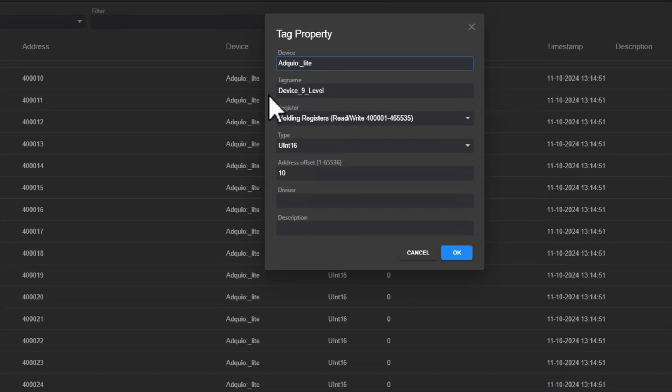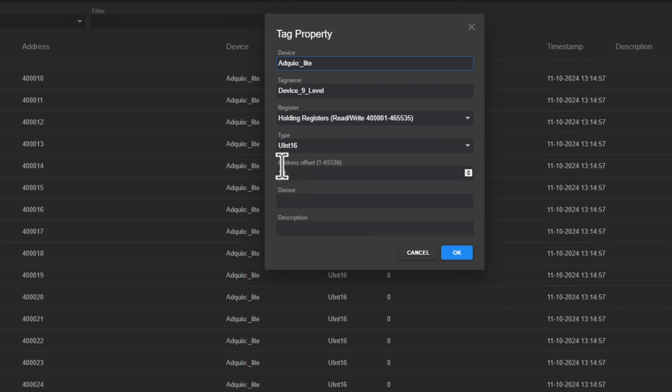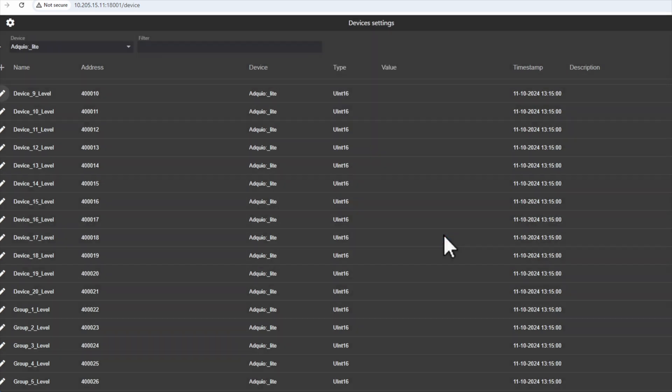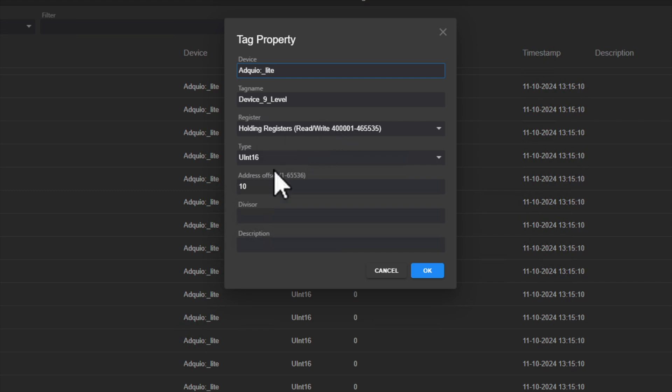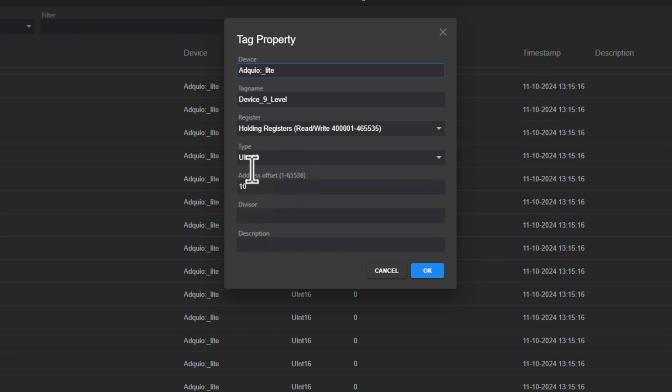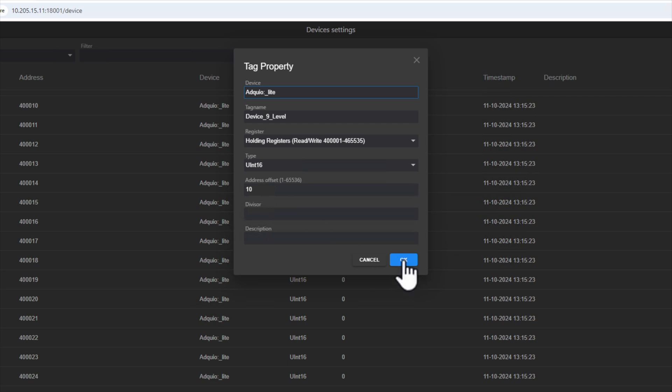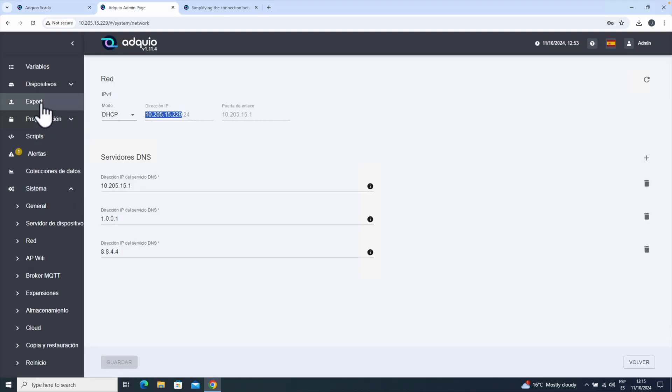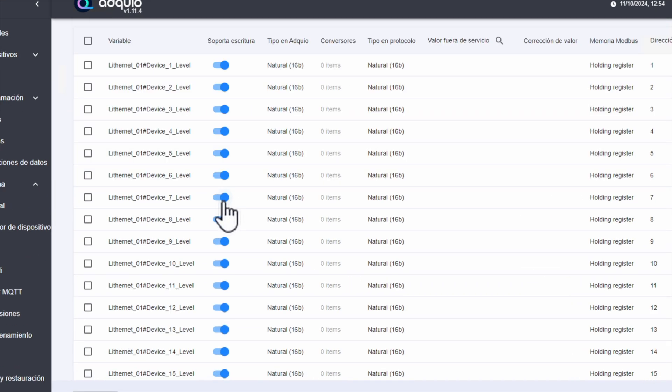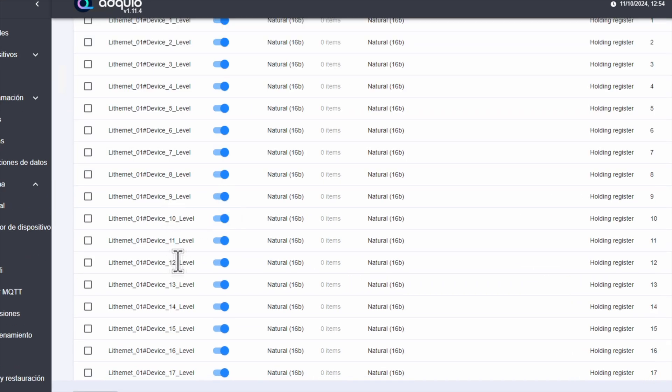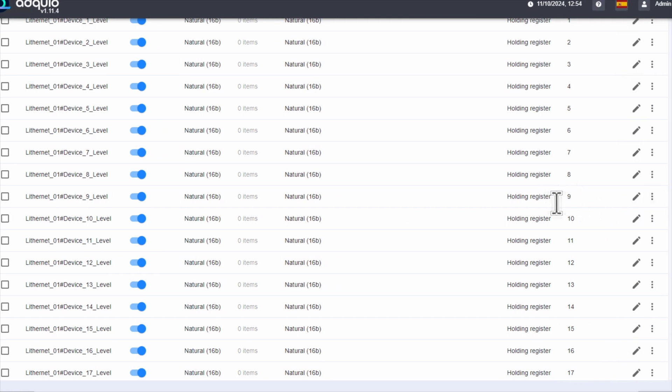So, if we look for this variable, Device 9 level in Adquio, you'll see that instead of address 10, it has 9, but this is completely normal. Similarly, if you want to add variables manually here, you should put exactly this same configuration. They are always holding registers in this case, always UInt16, because they were exported that way in Adquio, and when you need to write the address, you'll always write one higher than what you see in Adquio. Let's check it out. The Device 9 level, as you can see in Adquio, has Address 9.